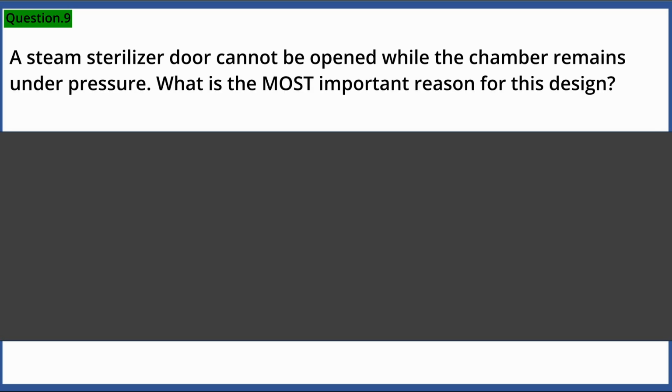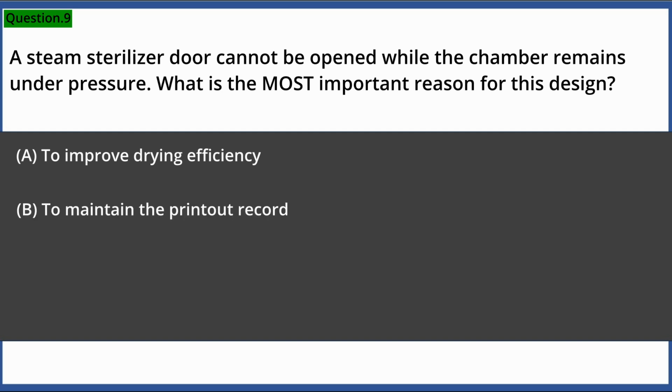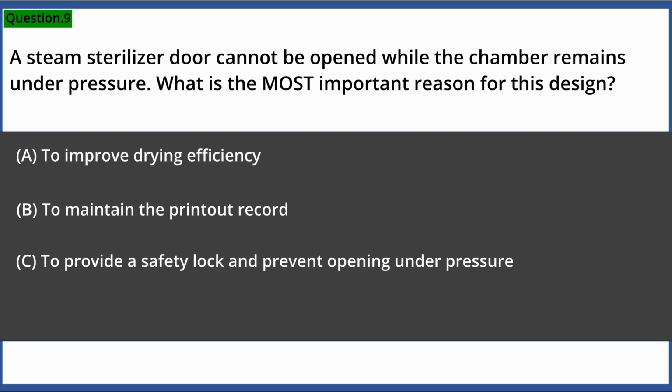A steam sterilizer door cannot be opened while the chamber remains under pressure. What is the most important reason for this design? A. To improve drying efficiency. B. To maintain the printout record. C. To provide a safety lock and prevent opening under pressure. D. To reduce bioburden in the chamber.